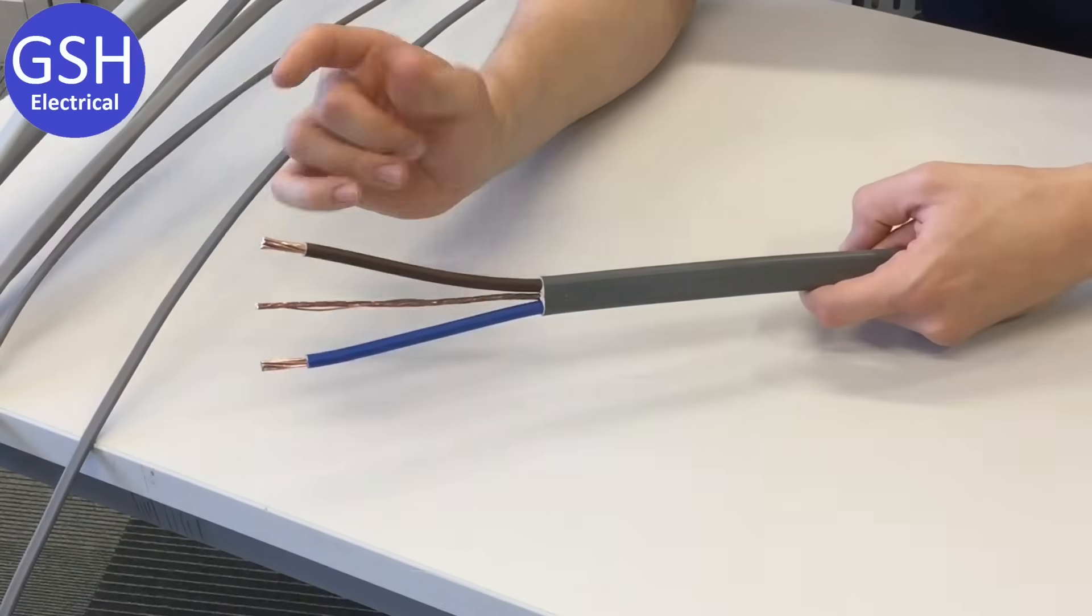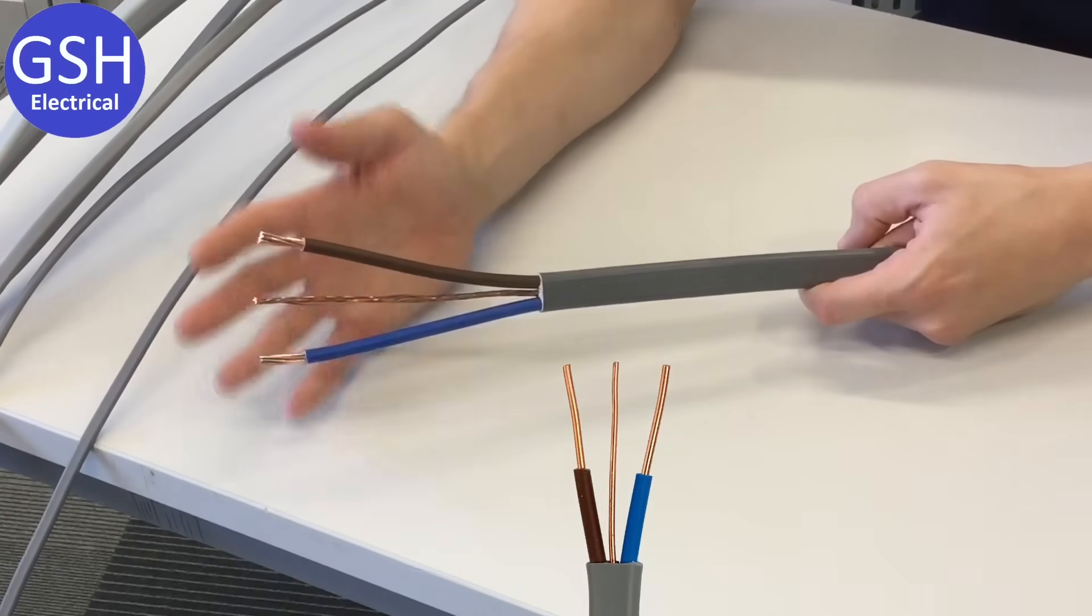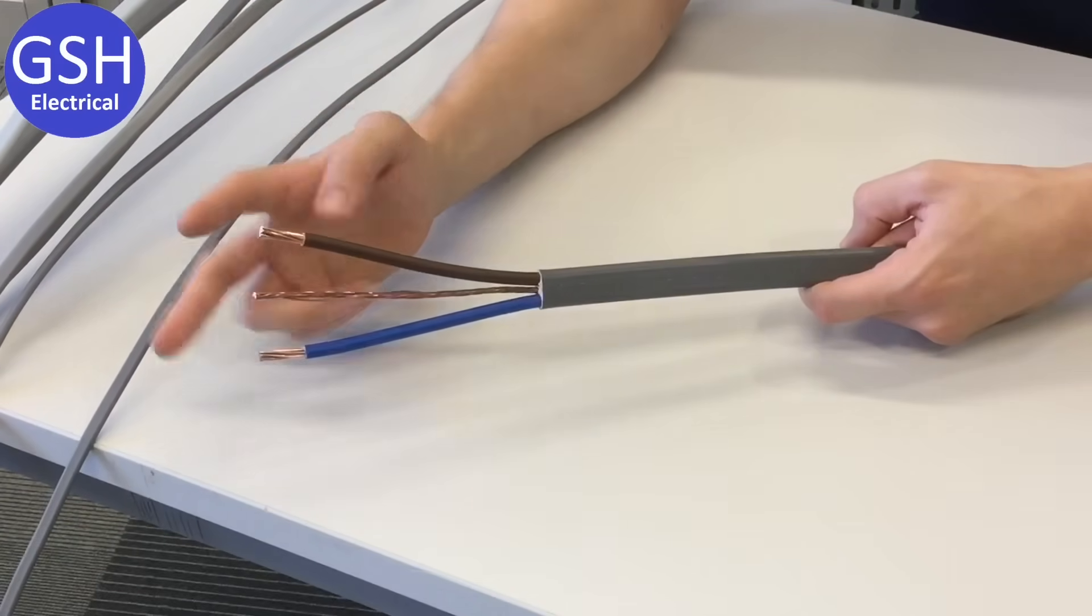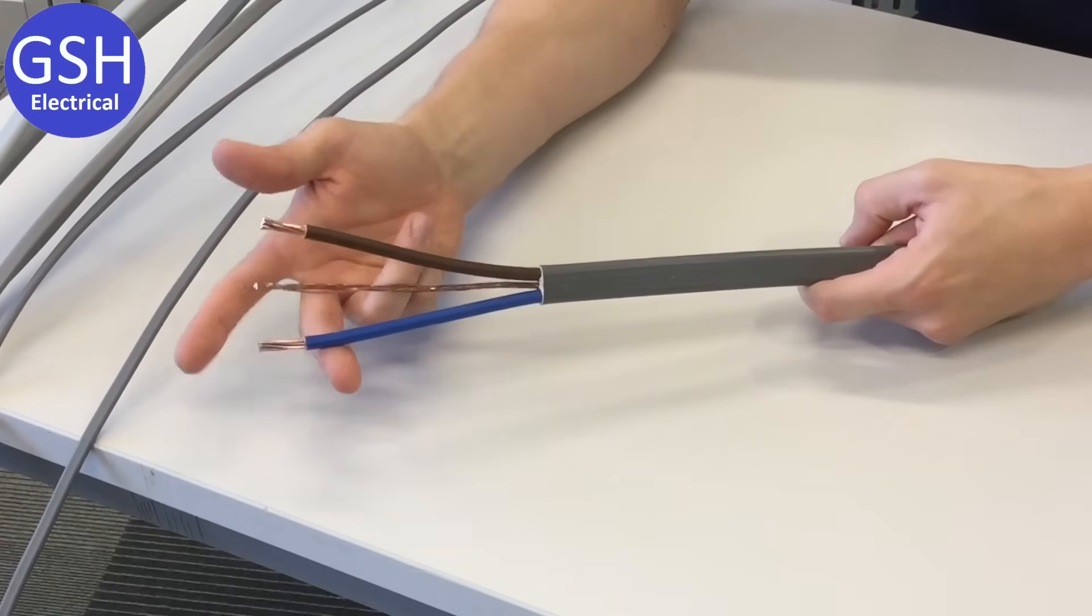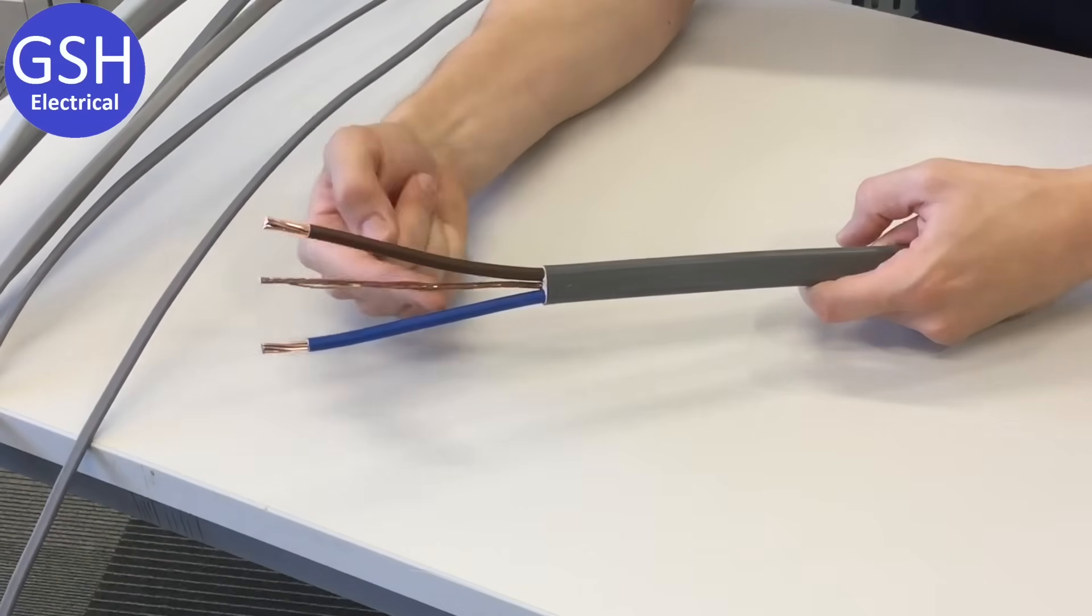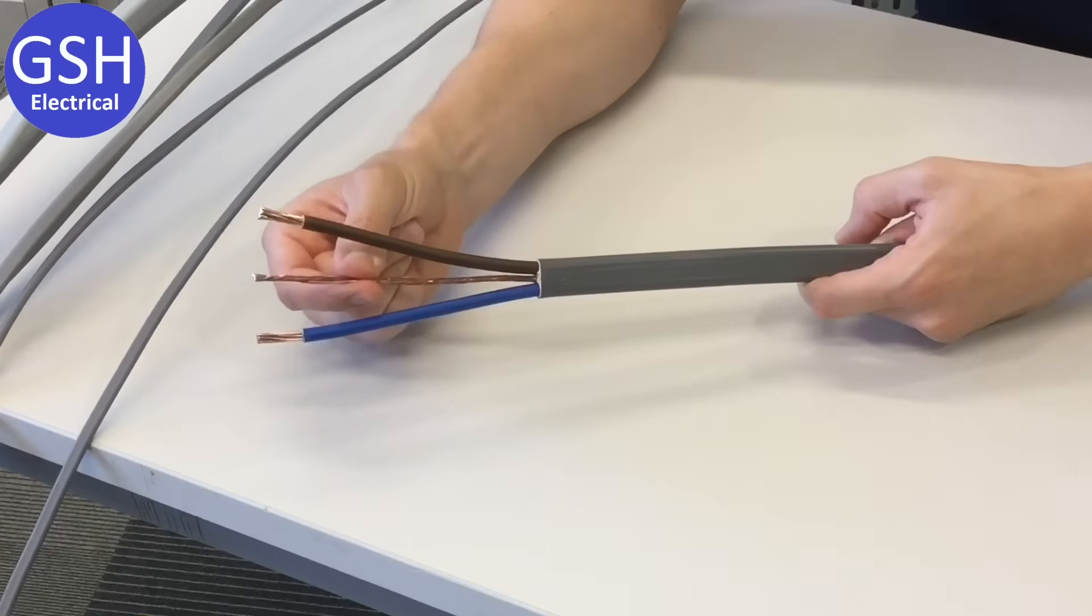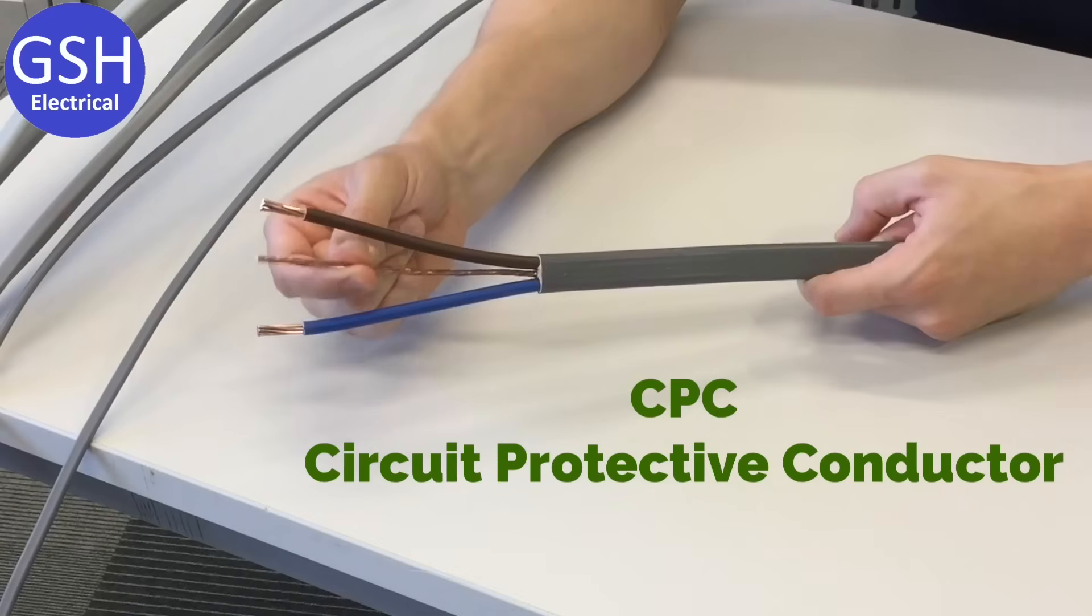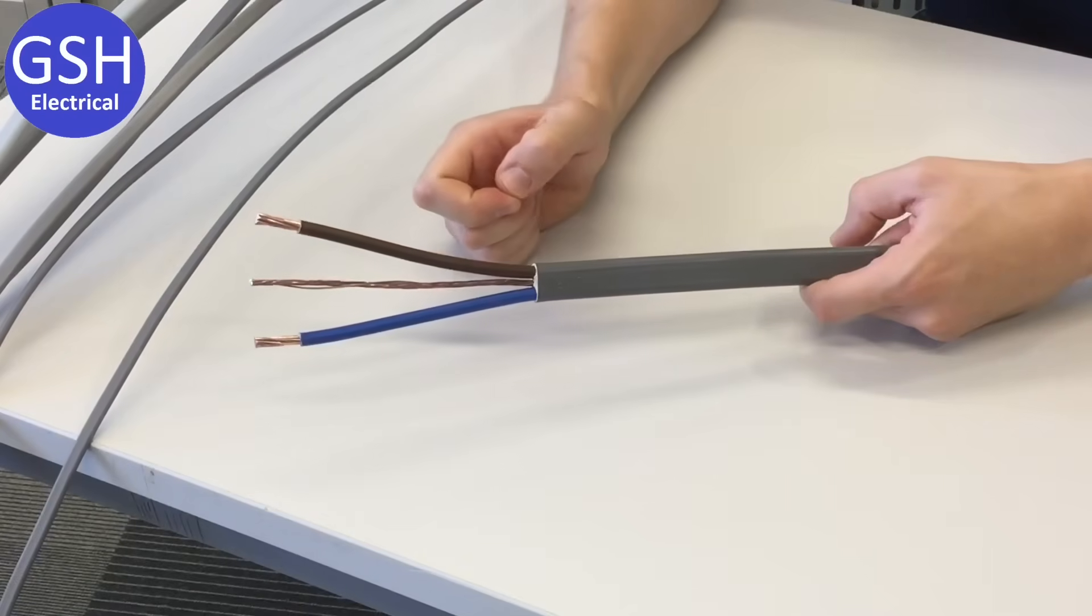We then move on to the part where we talk about this being twin and CPC. Now you may be looking at this cable and thinking, but Joe, there's three conductors there. We only actually count the insulated conductors. You can see here that we've got one insulated conductor, two insulated conductors, so that's where our twin comes from. And then we've got CPC, which is this conductor in the middle. Again, you'll often hear this be referred to as earth. This is not an earth cable, an earth conductor. This is technically a CPC, but again the difference between those will be covered in another video.